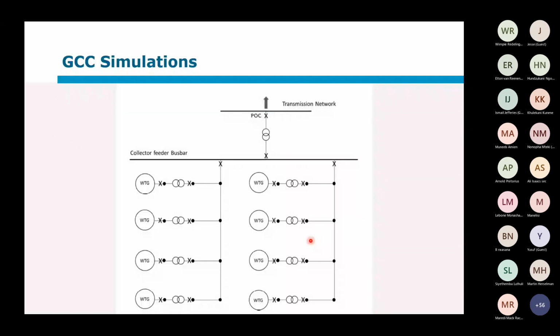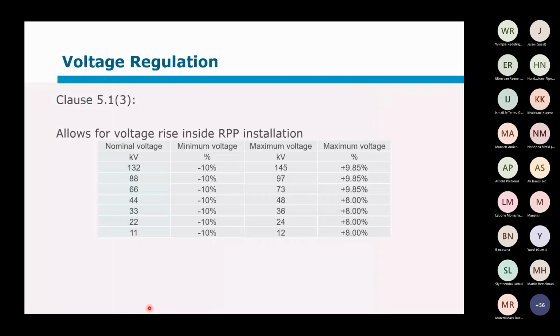And it means that at all the equipment at the furthest ends, this voltage must not be too high that the customer's generating equipment gets damaged or trips off, for that matter. What is implied here is that as the distributor, the voltage at this point shouldn't exceed these values.